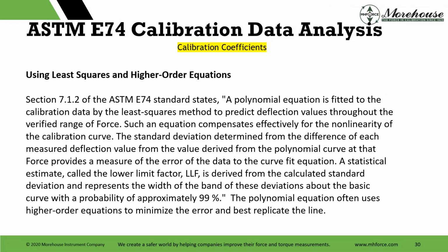So, using least squares and higher order equations, here's from E74. A polynomial equation is fitted to the calibration data by the least squares method to predict deflection values throughout the verified range of force. Such an equation compensates effectively for nonlinearity of the calibration curve. The standard deviation, determined from the difference of each measured value from the polynomial curve at that force, provides a measure of the error of the data to the curve fit equation. A statistical estimate called the lower limit factor is derived from the calculated standard deviation and represents the width of the band of these deviations about the basic curve with a probability of approximately 99%. NIST did a whole bunch of testing and studies on this. The polynomial equation often uses higher order equations to minimize the error and best replicate the line. So we use that equation.